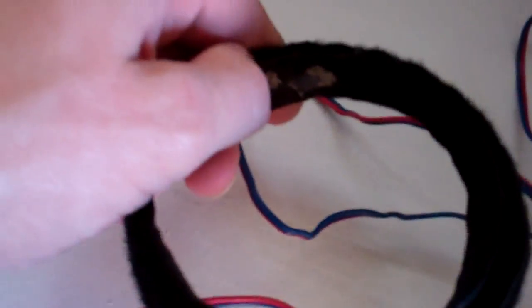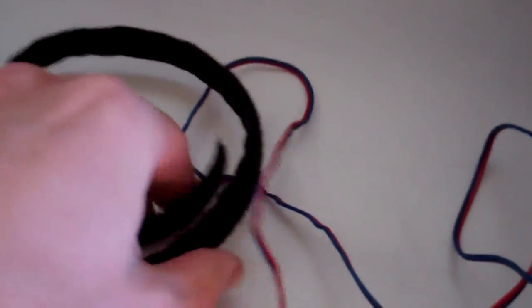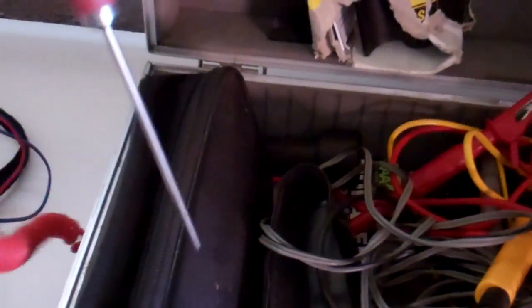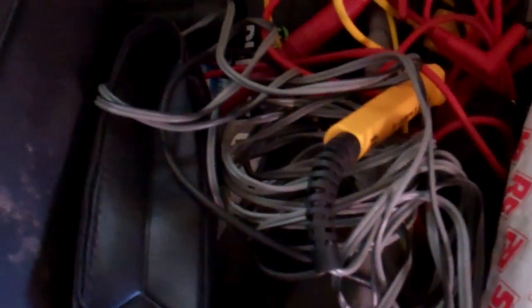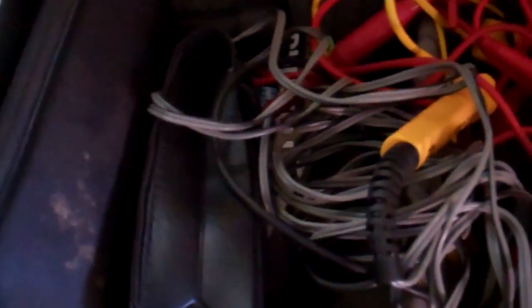It's not that accurate, but it's better than nothing. I've got another one I got first, which is this sensor here. This is Velcro. You can Velcro it around any size pipe or around anything you like, really. Right, and then we've got a waterproof probe. Quite often I use that one for testing milk temperatures, or you poke it in under the insulation round by the expansion valve, just leave it in there for 5-10 minutes and it'll stabilise and read the same temperature.